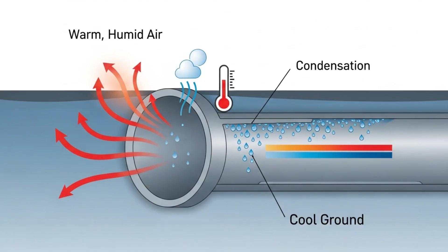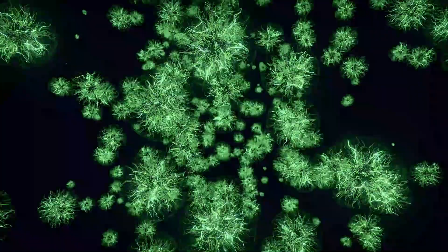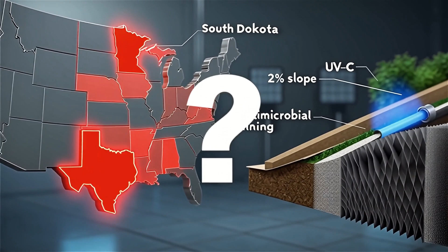The most common objection raised against earth tubes is moisture and air quality. The argument goes like this. If warm, humid air travels through a cool underground pipe, condensation can form inside the pipe. That moisture could theoretically allow mold or bacteria to grow. And if contaminated air gets pumped into your home, that is a health risk. This is a real engineering consideration. It is not fake. And good earth tube designers have solved it completely with sloped drainage, antimicrobial pipe linings, filters at the intake, and UV sterilization at the outlet.